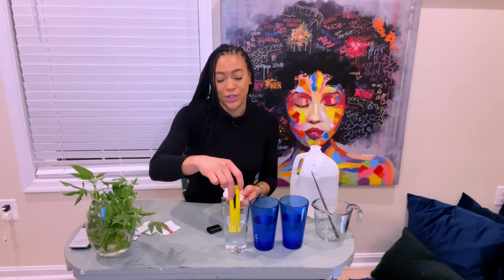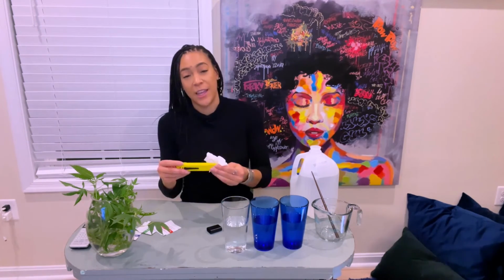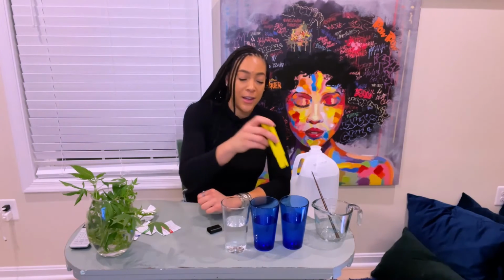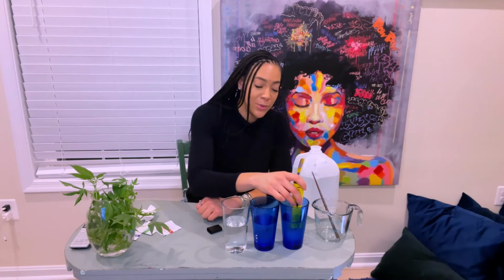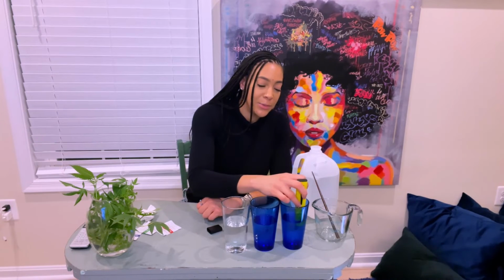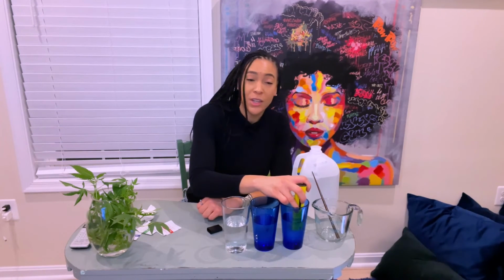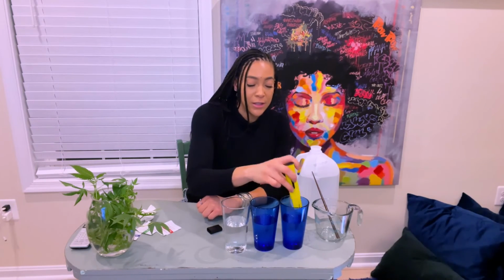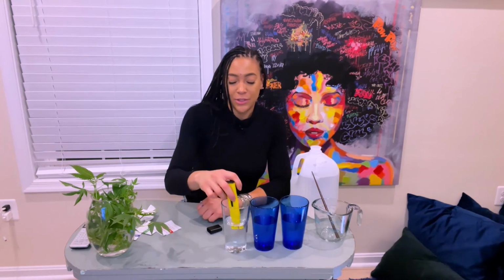And I'm going to take this out and give it a little zhuzh in the water and dry it off. Then I am going to put the meter into our 4.0 solution, let it settle a little bit, and then press 1, 2, 3, 4, 5, and it is calibrating, it says end, and it's giving me a 4.01 reading, which I'm totally cool with. So I'm going to just go ahead and dry that off again.